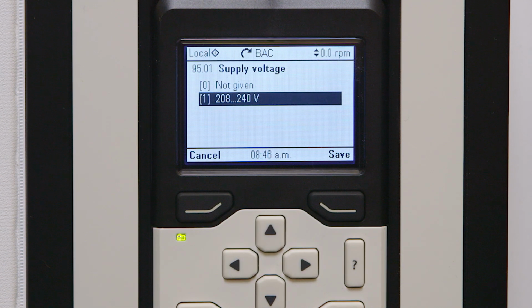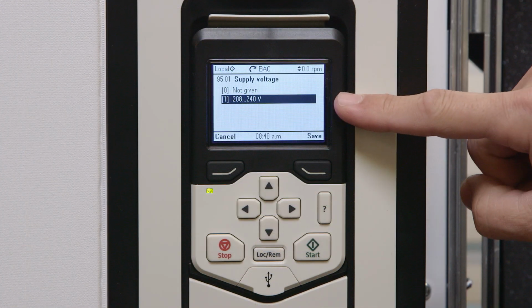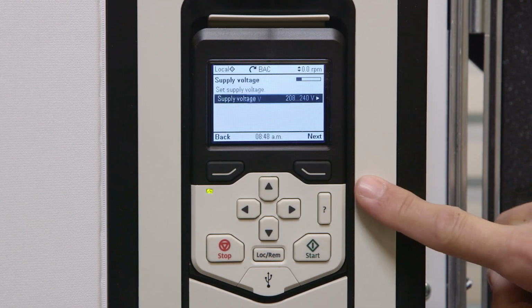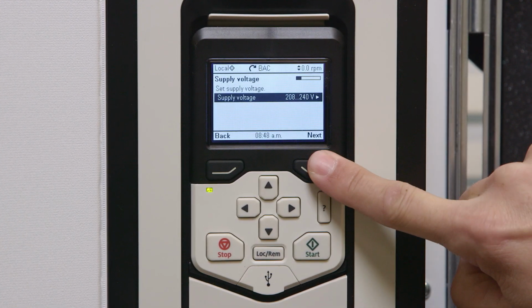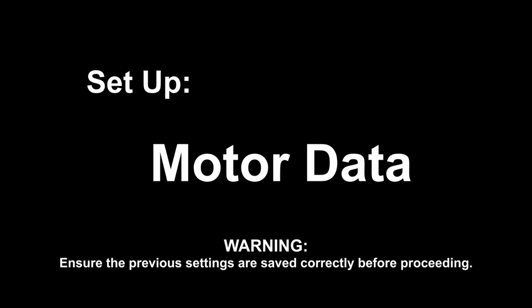The display will only show the option your drive is rated for. In this example, the system is rated for 208 to 240 volts. Make that selection. After selecting the correct supply voltage, press Save. Then press Next. Set up motor data. Once the supply voltage is set, the VFD will prompt us to set the motor data. In this section, it is important that you ensure the previous settings are saved correctly before proceeding.